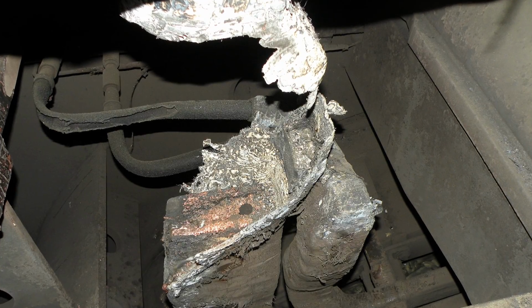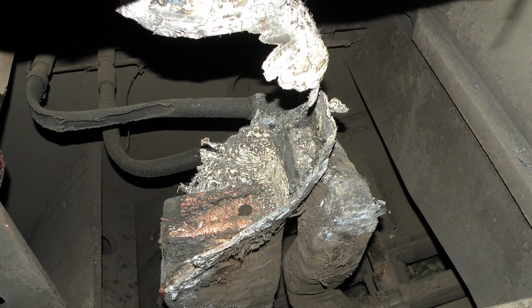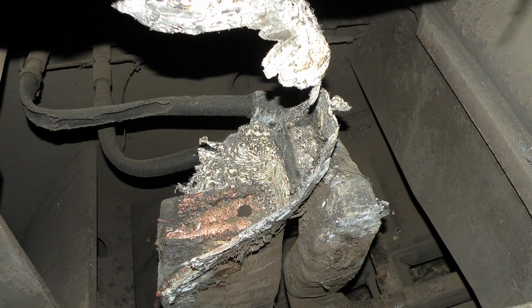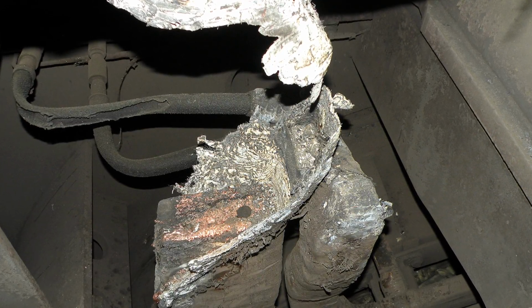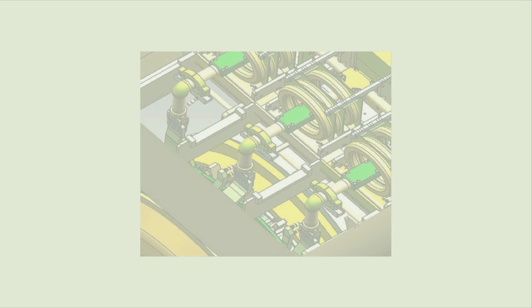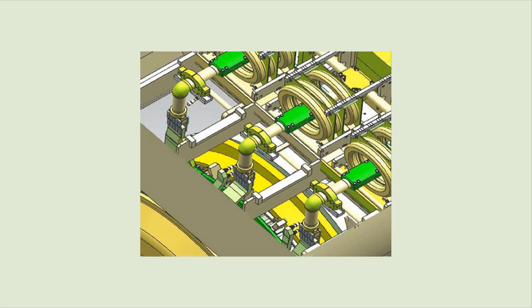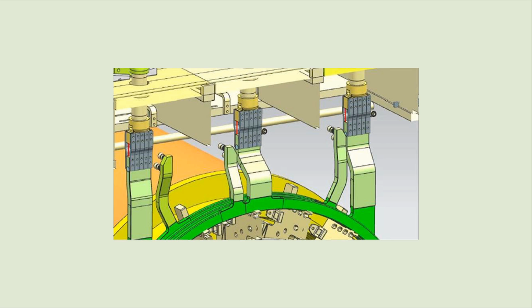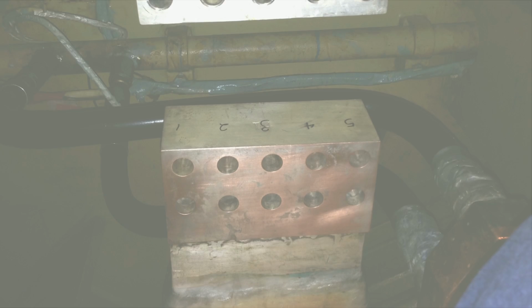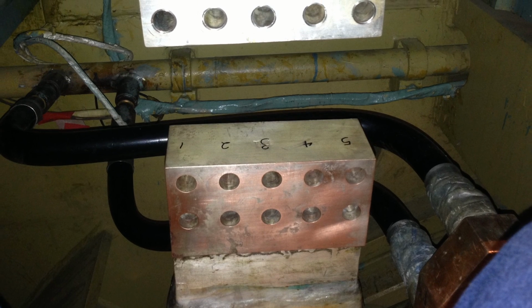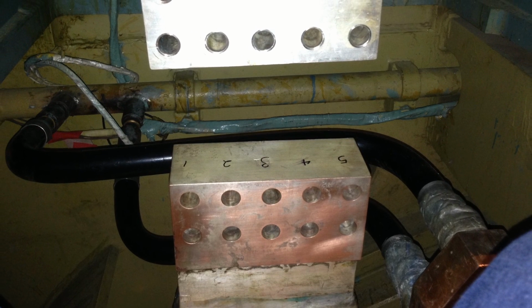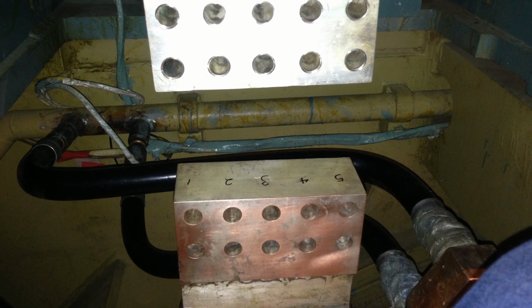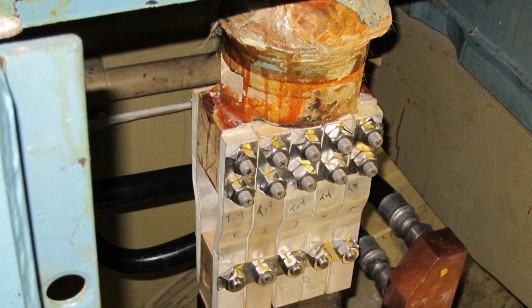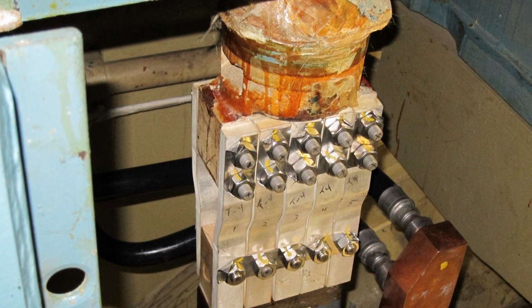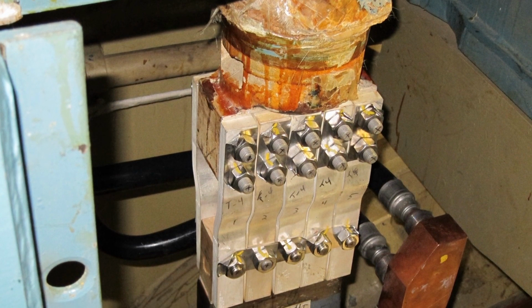Intermountain has recovered from the Unit 1 generator connector ring attachment failure. Repairs and modifications have been made to both units to prevent this failure from reoccurring. General Electric recommended modification of the bolted interconnection between the existing generator stator connection ring and the generator bus. The modification included the addition of an extension cap to each stator connection ring tang. The extension provided the addition of a second row of bolted fasteners for the flex leads from the stator connection ring to the generator electrical bus.